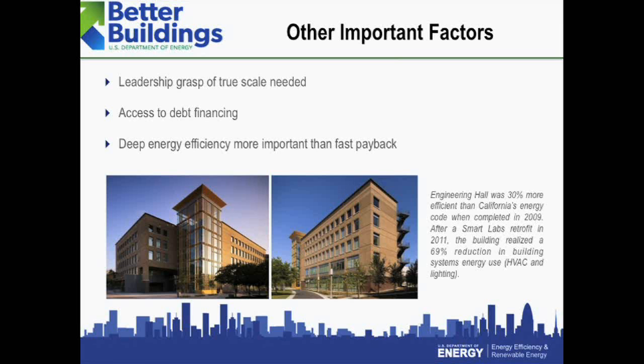The second kind of savings that I think we need to bring right out in the open, it's a little bit harder to nail down with such precision, but the truth of the matter is these deep energy efficiency projects actually solve a lot of what we call deferred maintenance problems. These are unknown, for the most part, problems that we'll find in building control systems, in heating, ventilating, and air conditioning dampers. They tend to be things in the mechanical room or not out in the open. These things are worth at least 10% additional savings on top of whatever kind of energy projection we see.